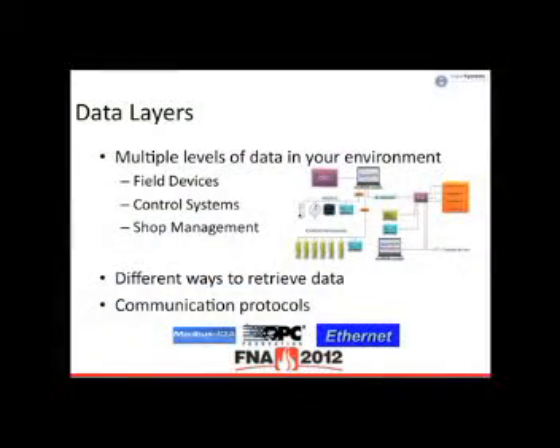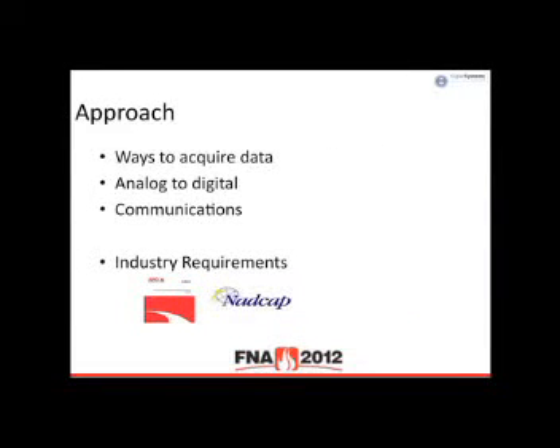But really what you're doing is you're taking advantage of all those discontinuous control systems and sensors and bringing them centrally into one system. And there's different ways to get that information, different communication protocols that can be taken advantage of. So when you look at your different ways to acquire data, you have things like analog to digital, just pulling an analog signal. Take a thermocouple, for example. Jumpering that information, turning that into digital information that you can put on a chart, or you can look at it in a tabular format. Or you can use communications. All right, if you're using communications, a protocol that you can actually talk to those discrete controllers or to the PLCs or whatever the control system is, there's a significant amount of information that can be gathered from that and then utilized for other things.